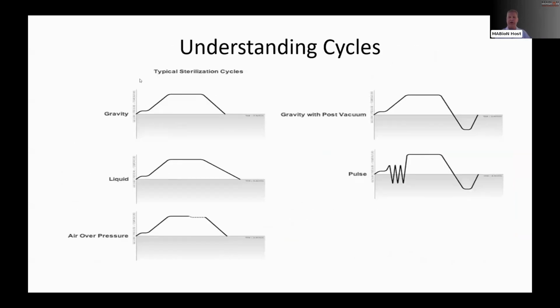I have this basic chart here, and we're going to focus on three of them: the gravity, the liquid, and the pre-vac, which you'll see up here as a pulse. Especially if you get any liquids in here, and I've had people run the gravity cycle by mistake for a liquid. This little section here is generally where they do the purge. The purge preheats the autoclave. It takes all the cool spaces out of the chamber, and then it starts working to warm up whatever is in there.